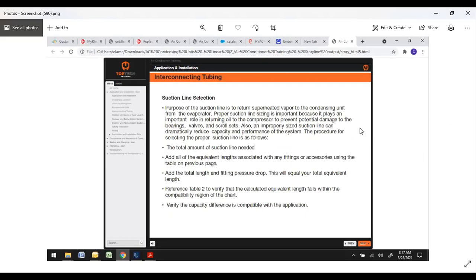Your suction line selection. The purpose of the suction line is to return superheated vapor to the condensing unit from the evaporator. Proper suction line sizing is important because it plays an important role in returning oil to the compressor.